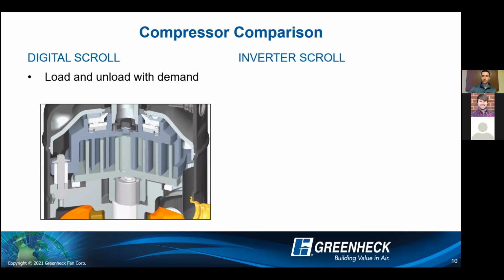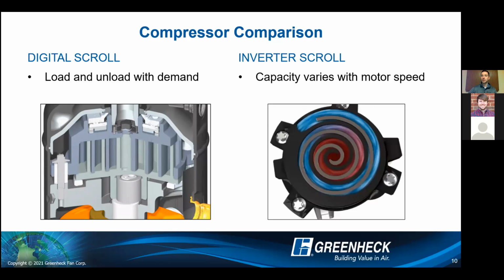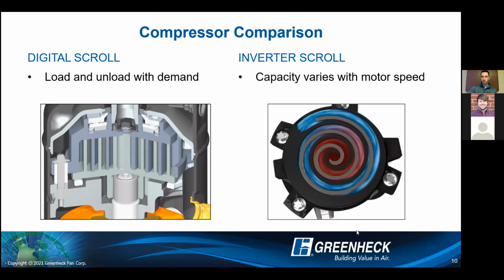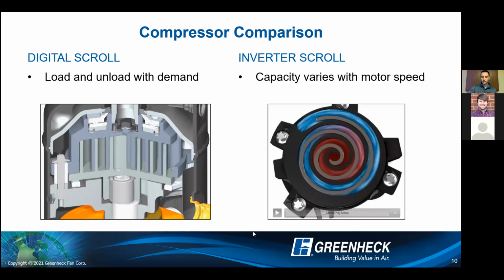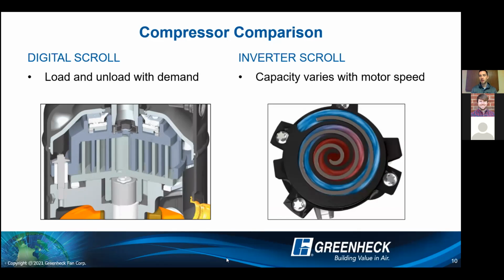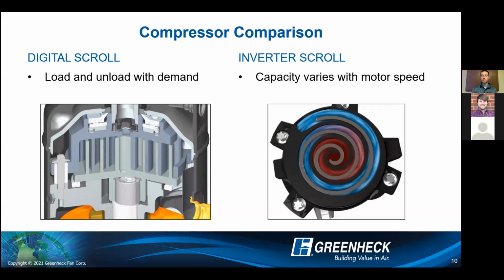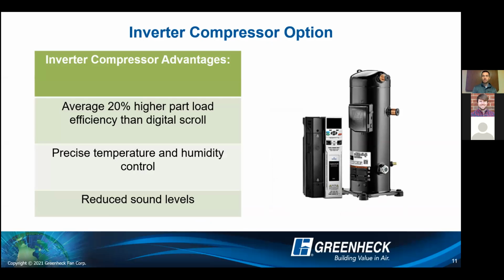So inverter scrolls, now this capacity is really varying based on motor speed. See if I can play this video. I don't know if it's going to work, but basically what the VFD does is it's going to actually slow down that frequency. So if it's again 50%, we can slow down that motor to 50% instead of just loading and unloading that compressor. So you get really high part load efficiency values. And there's a number of other advantages, but it's about 20% higher in that, let's just say IEER value, compared to the digital scroll.